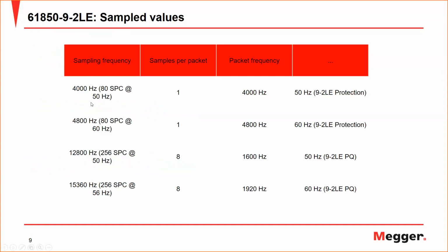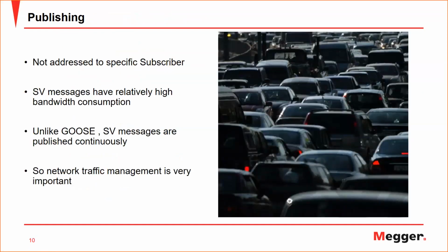As I mentioned earlier, for the 50 hertz, we have the 4000 hertz packet frequency. And for the 60 hertz, it's 4800, because in both these protection requirements, we have 80 samples per cycle. So the cycle for 50 hertz is longer than the cycle of 60 hertz. And for power quality applications, that sampling frequency becomes much higher. As I mentioned, these messages will be published, so they are not specified to a certain device in your Ethernet network. It's not addressed to a specific subscriber, so anyone can really see them or subscribe to these published messages.